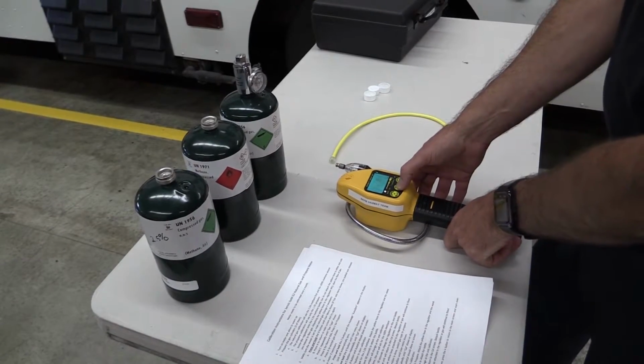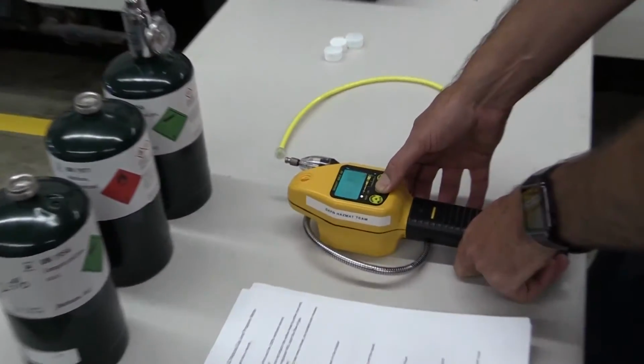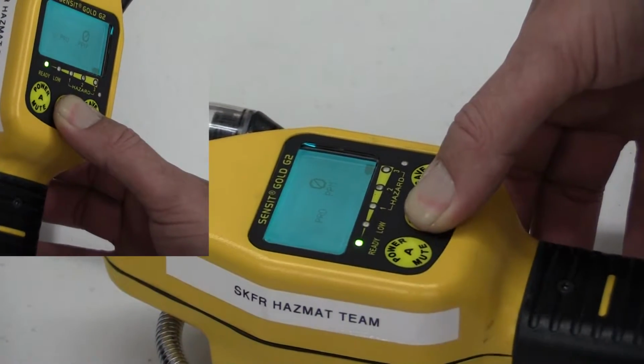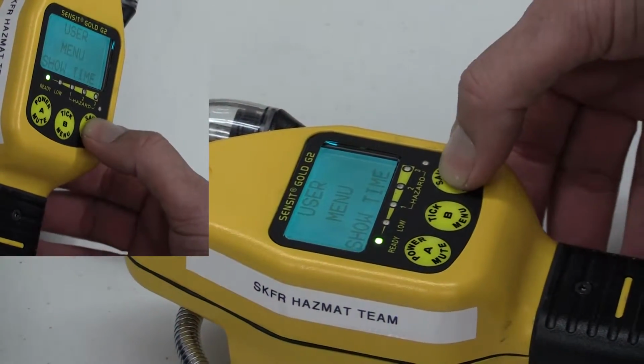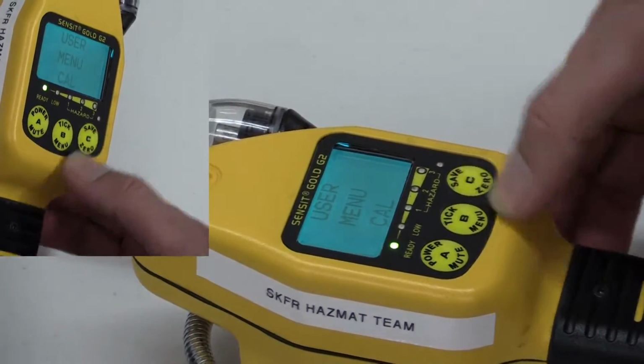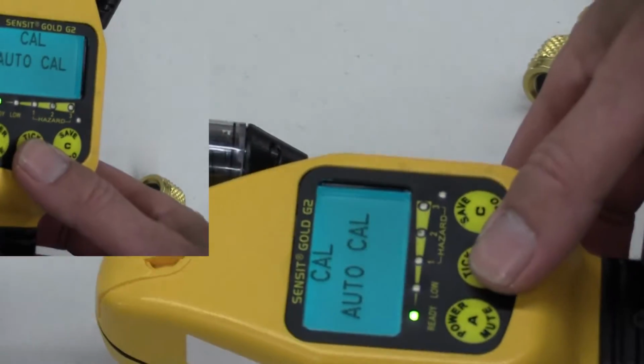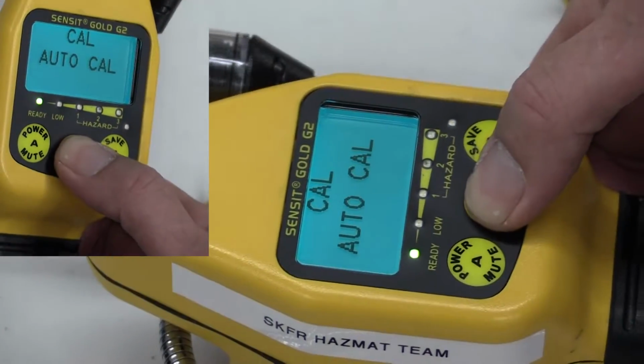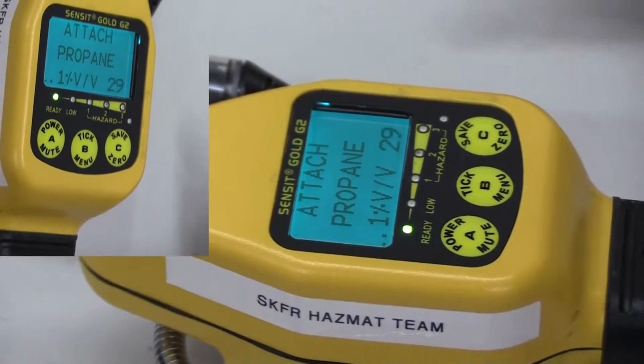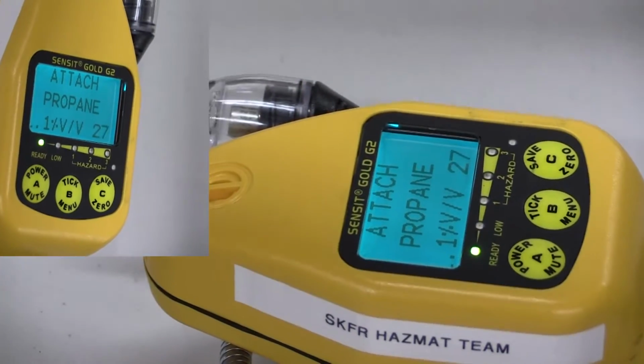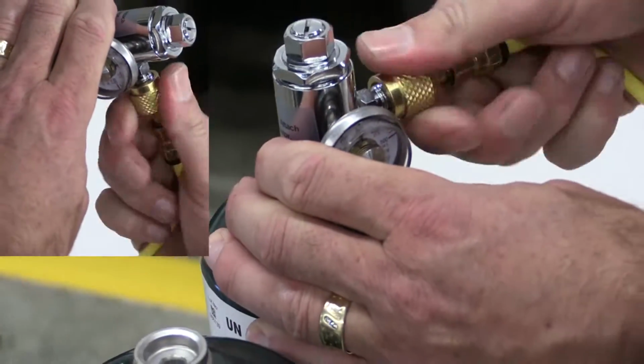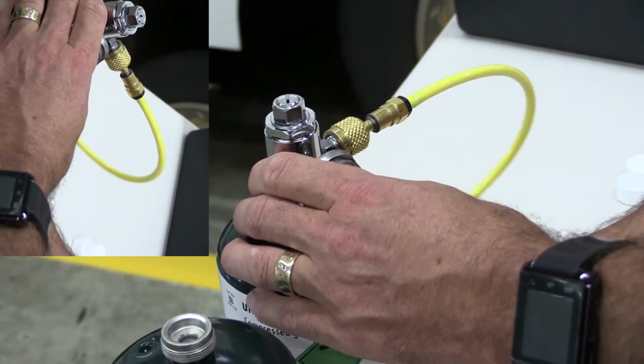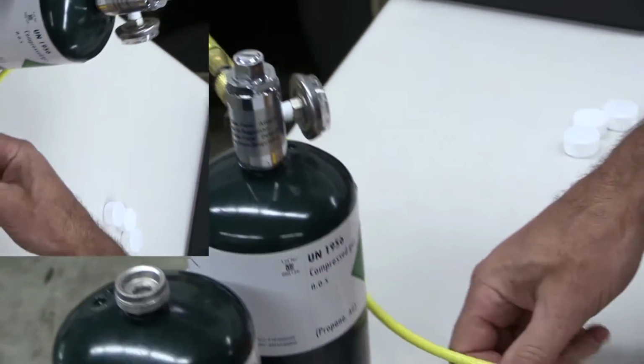Now we need to go back through the calibration mode to do the propane side. Press and hold the B button. Go to Cal, Auto Cal, and now it's going to ask for the propane to be attached. Just like we did before, we attach the yellow hose and attach it to the unit.